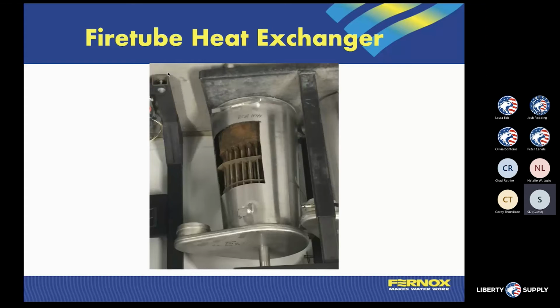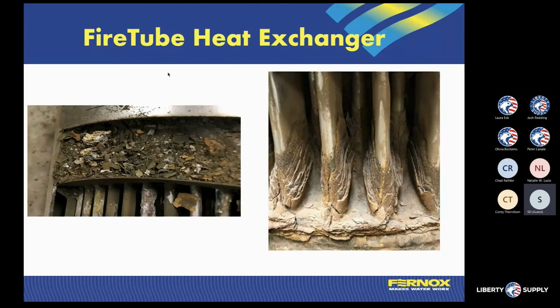So these are things that we're seeing as realities. This is a cutaway from the manufacturer to see what that looks like. These are other heat exchangers exposed to poor water quality. And again, you have to remember the burner is trying to put energy in through these tubes and put that into your fluid.